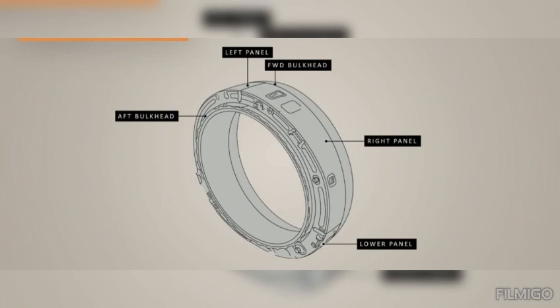At the top of the outer barrel, a ventilation scoop decreases the temperature of the fan cowl compartment zone. The air from the ventilation scoop goes through the distributor assembly to make sure that there is a good airflow. This will not let flammable liquid collect at the distributor. This airflow will also decrease the temperature in the fan case compartment. Airflow also ensures the extinguishing agent is equally spread in the fan cowl compartment if a fire occurs.